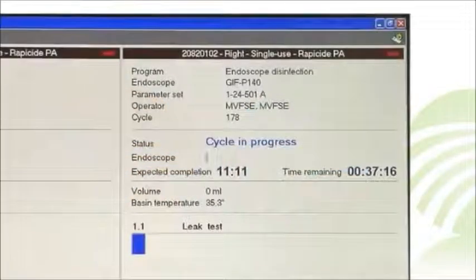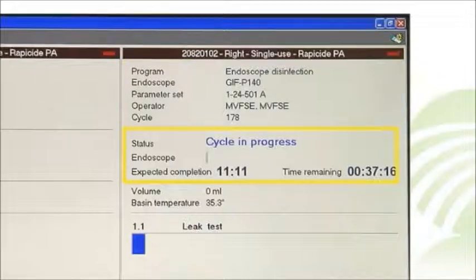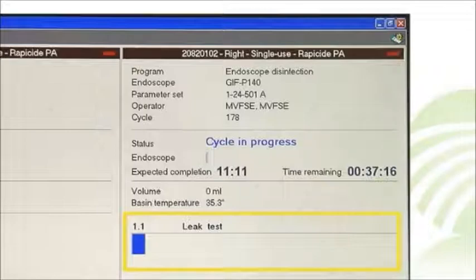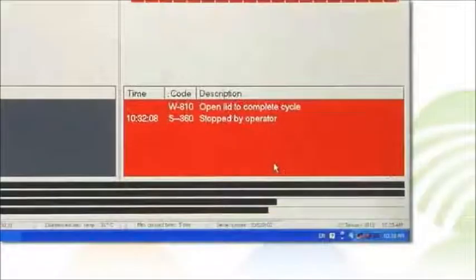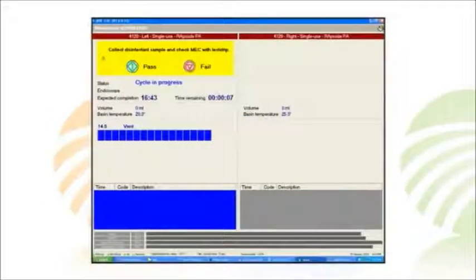The progress of the reprocessing cycle is presented on the user screen. Find the endoscope number, operator ID, and cycle number for that basin. Status, expected completion, time remaining, and phase are noted next. Program messages including error messages will be indicated in the box noting the time, error code, and description. When the disinfection process is complete, the program screen will prompt the operator to test the high-level disinfectant MEC with a test strip.